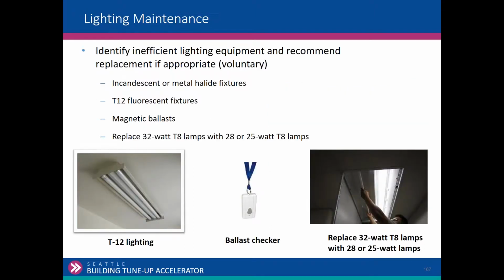On the voluntary maintenance side, obviously if you notice there's a whole bunch of incandescent fixtures and T12 lamps, there's an opportunity there, or magnetic ballasts, or fixtures that have burned out lamps. It's a voluntary measure, but it's something that you can note as an opportunity for them. Replace with LED, put in occupancy sensors. Those are all opportunities. Not required, but a potential opportunity for the owner to pursue.